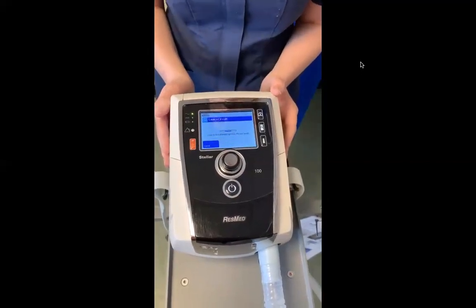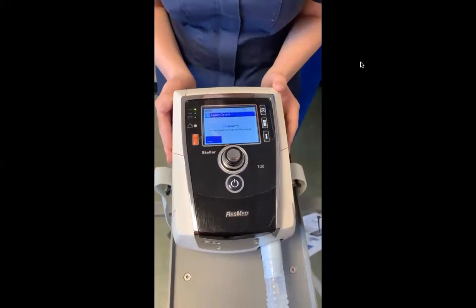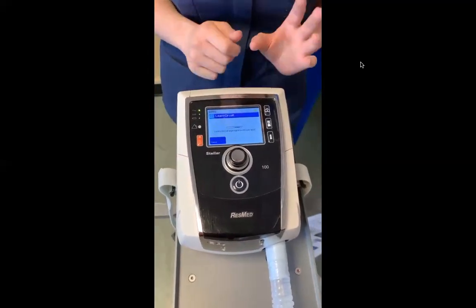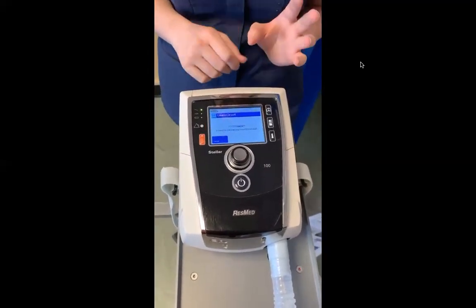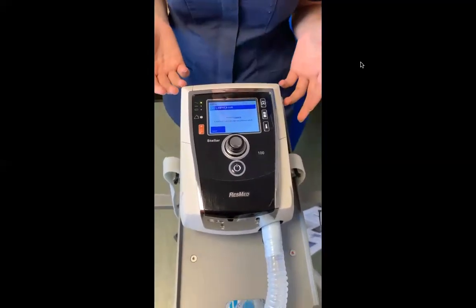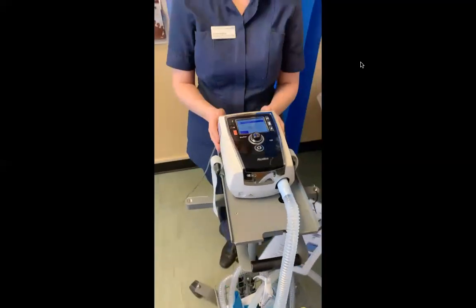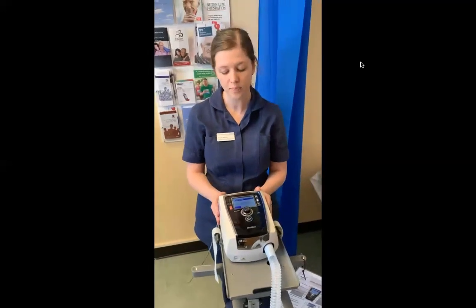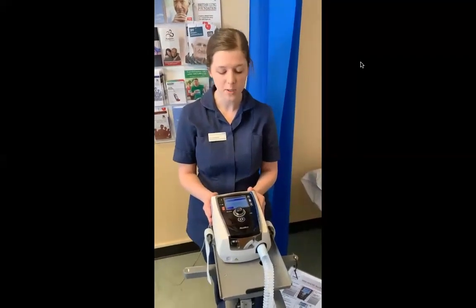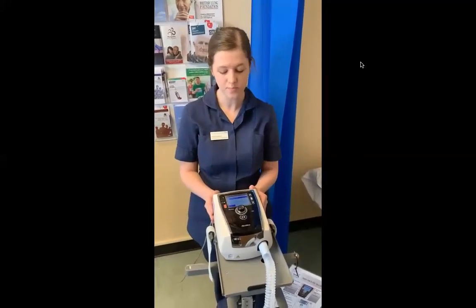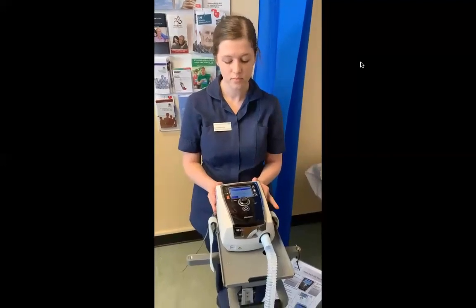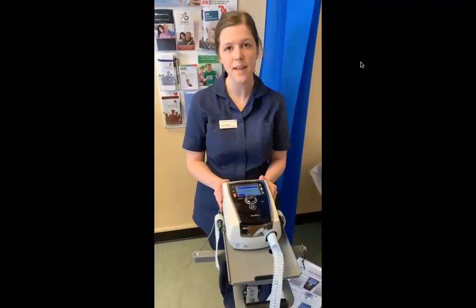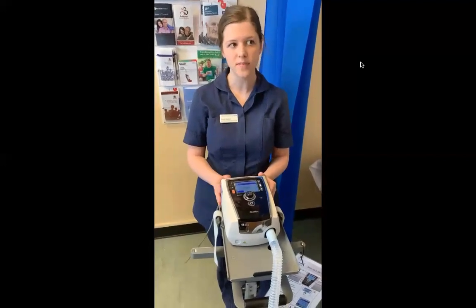and it will let you know if it's safe. I would also always say if it fails the first time, check all your equipment, make sure that it's all on tightly and it's all on the correct way, and try again. If it then fails again, then look to get new equipment and see if anything is faulty. So we'll just wait for that to complete. It only takes a minute or so. You should do this in between every patient and any time you change the ventilator tubing.